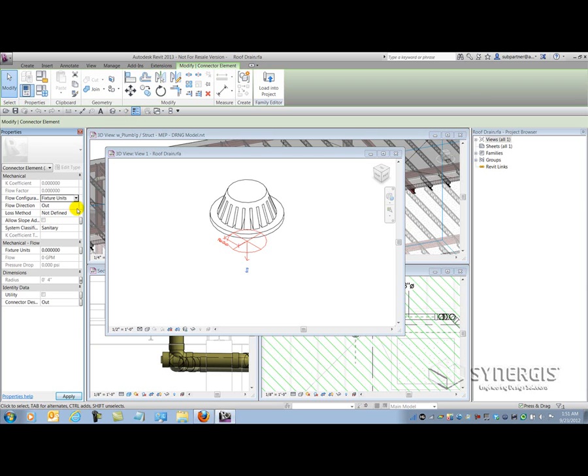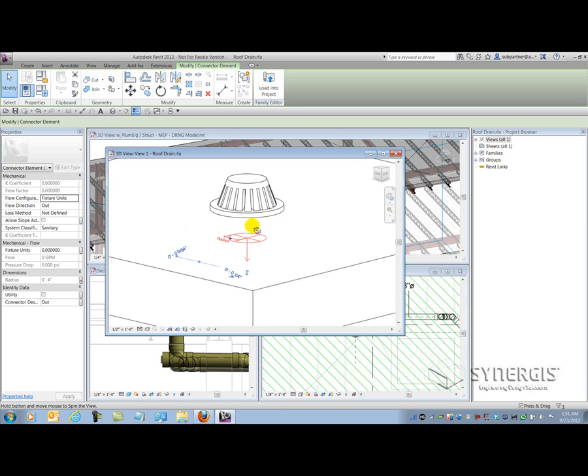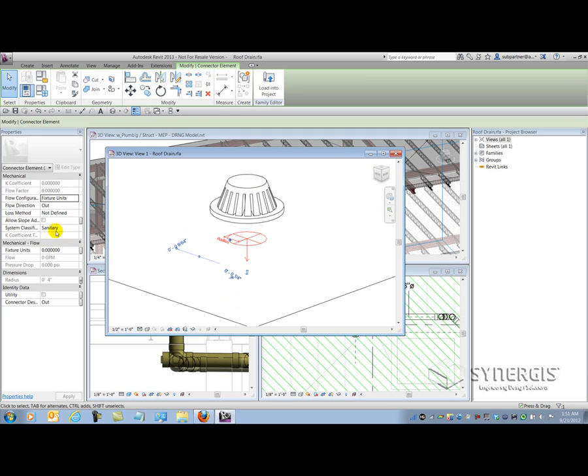We're going to use fixture units loosely because it's actually going to be square feet in our case, since we're using surface area of rainwater. With that general understanding, let's look at the connector and how flow is going to be interpreted. Water is going to drain into the dome and then out the connector into the pipe. The arrow here does not indicate flow — it just indicates the side that the pipe will connect to. My system classification is sanitary, and then I get to the fixture units parameter. This is where the magic starts to happen.